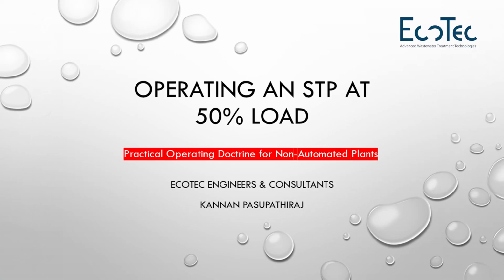Operating a sewage treatment plant starts not at the design load, but at a very low load. This is where real engineering begins. Most designers confidently explain performance at 100% design flow, but in reality, most sewage treatment plants operate at partial load, 20, 40, 50%, sometimes even much lower. And that is exactly where they fail.